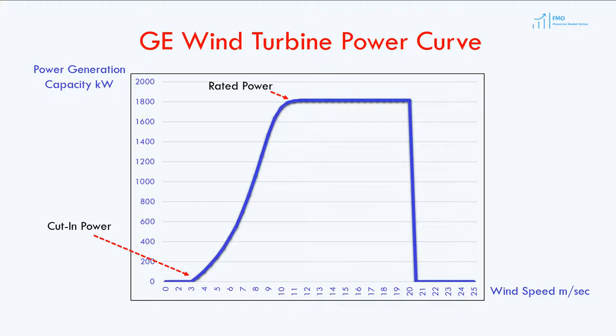Remember how in the previous lesson we talked about rated or nameplate capacity, which represents the maximum potential energy that wind turbines can generate. The rated power on the power curve represents this maximum potential energy. Finally, at wind speeds above 20 meters per second, the rotor stops in order to prevent damage — this point is known as cut-out power. Cut-in, cut-out, and rated power depend on the turbine and turbine manufacturer.